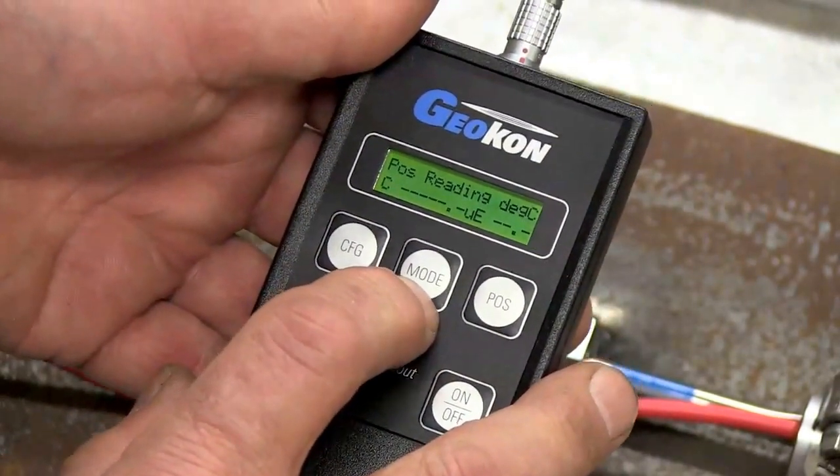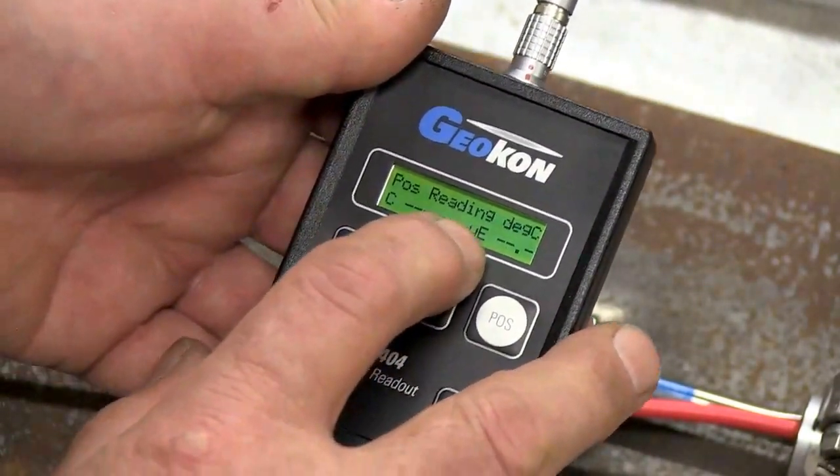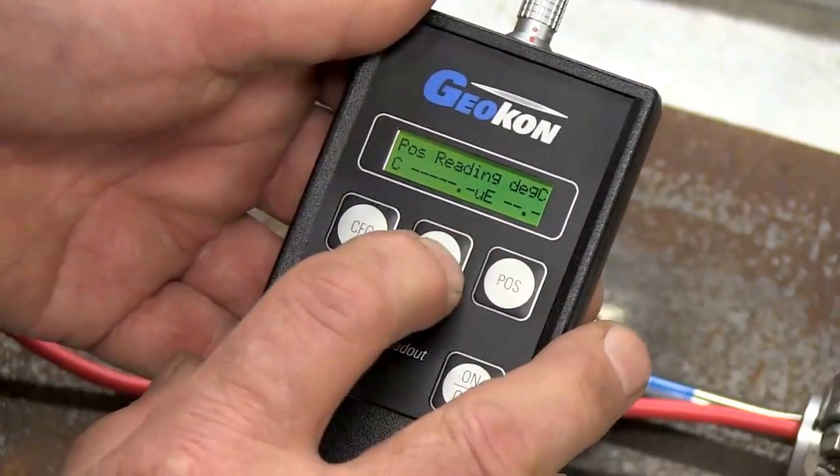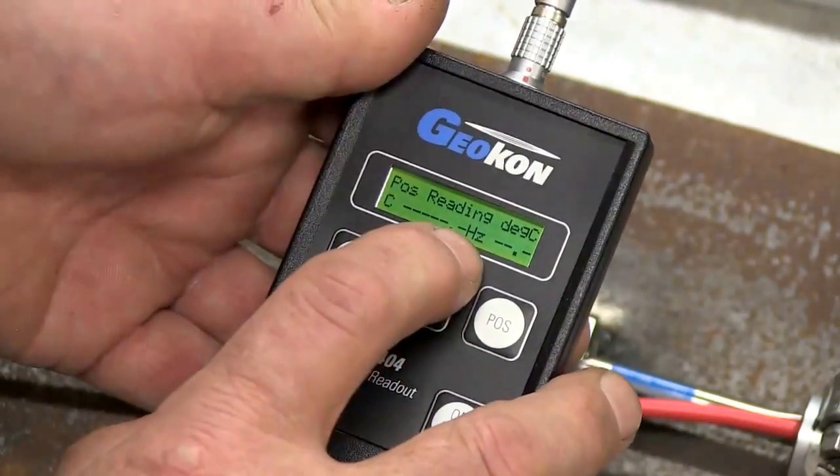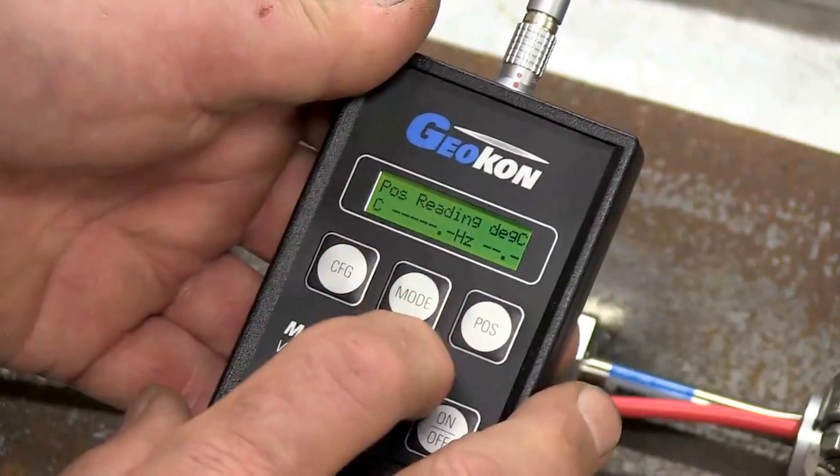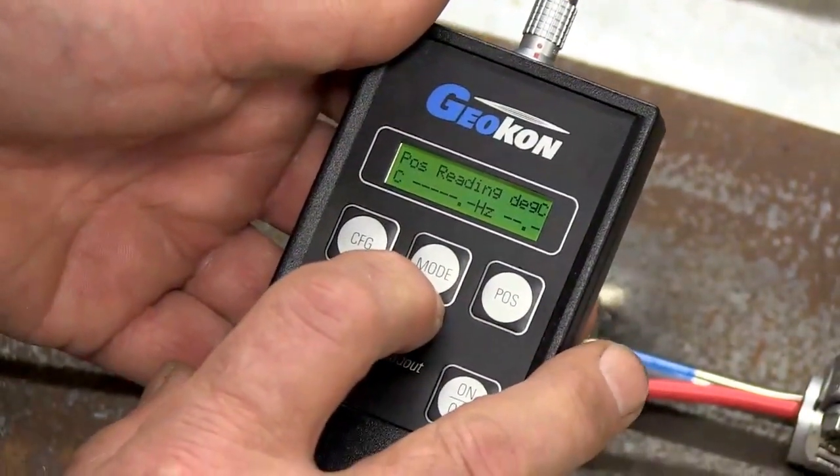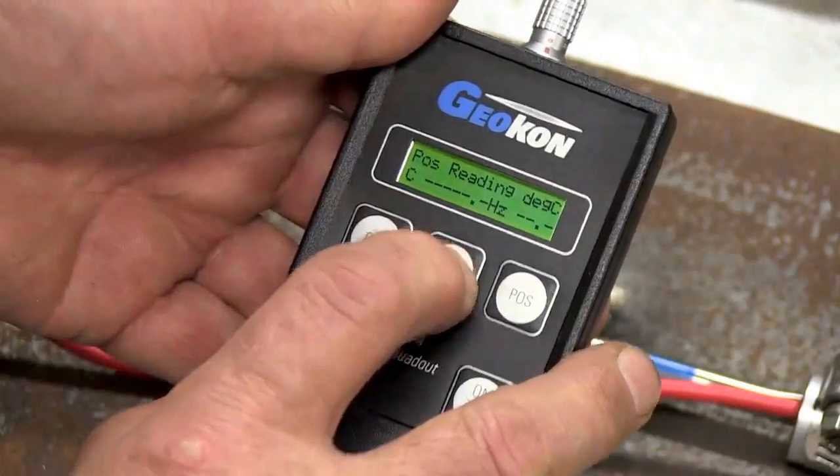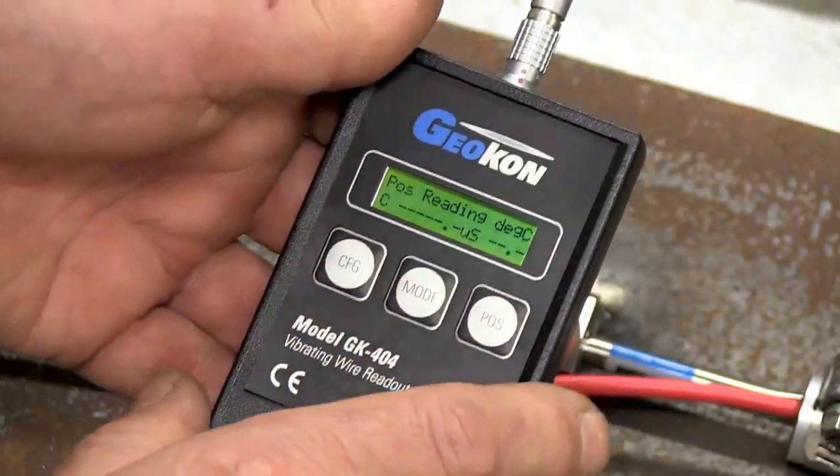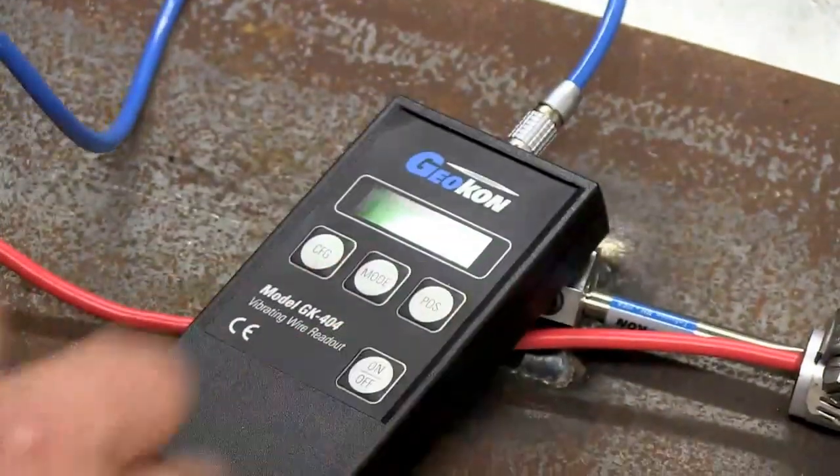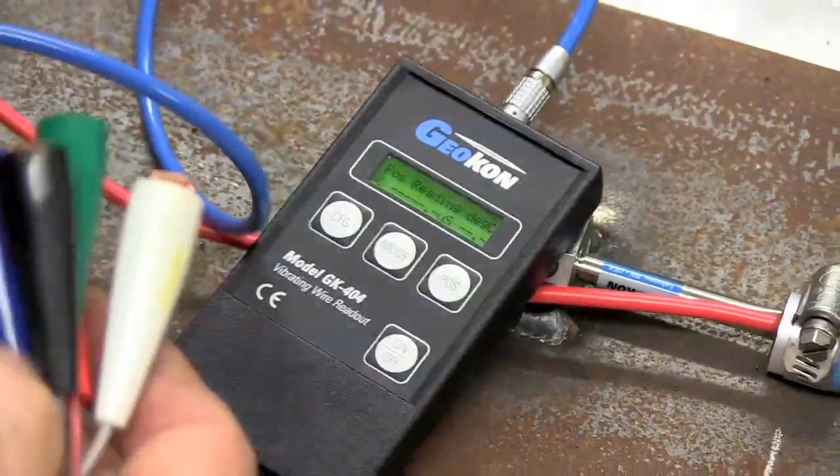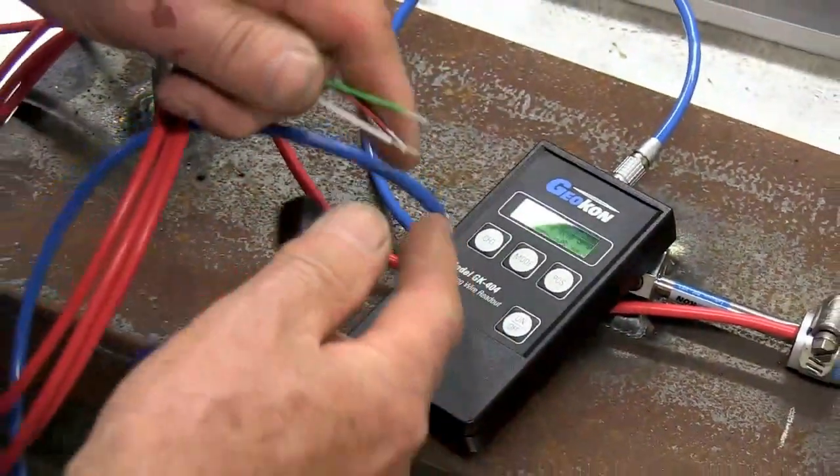In this case, we want microstrain, which is what that symbol means. The other mode might be hertz, which would be the frequency. But we want, at this time, to read it out in microstrain. So we set it to microstrain. Then, we connect the leads. A very simple operation, color for color.